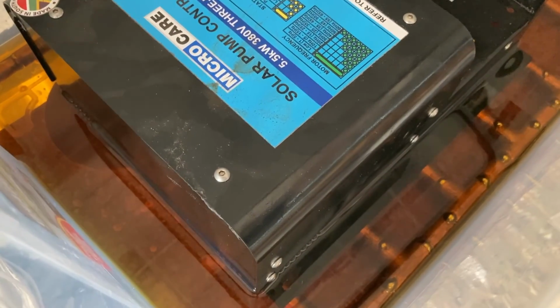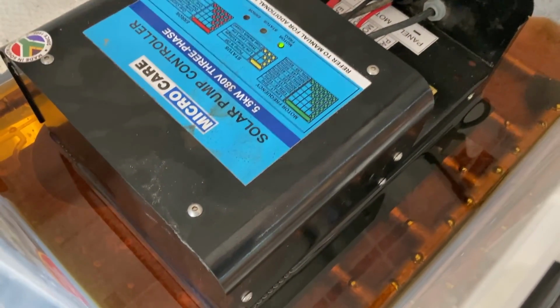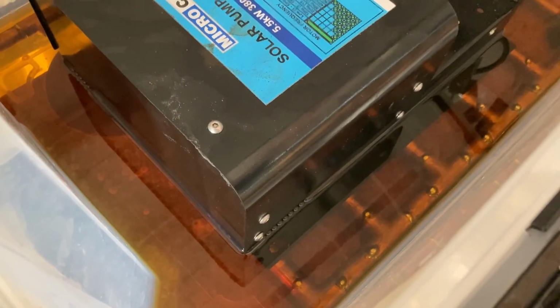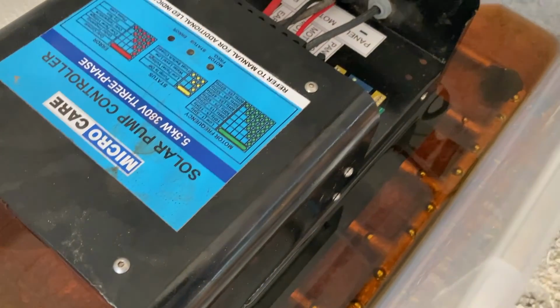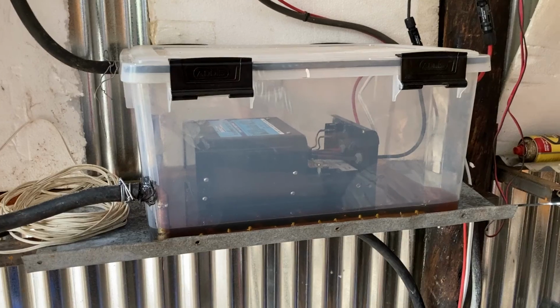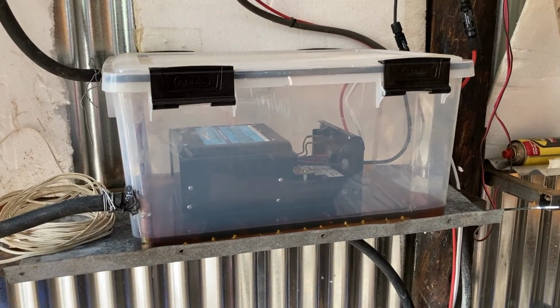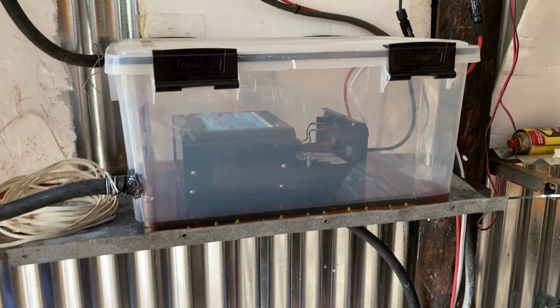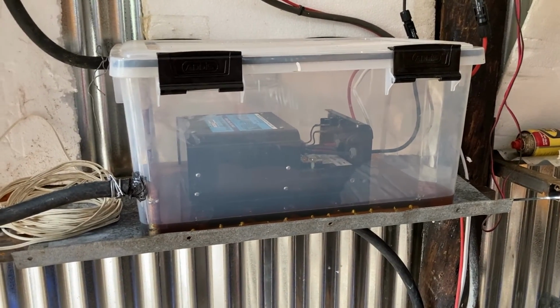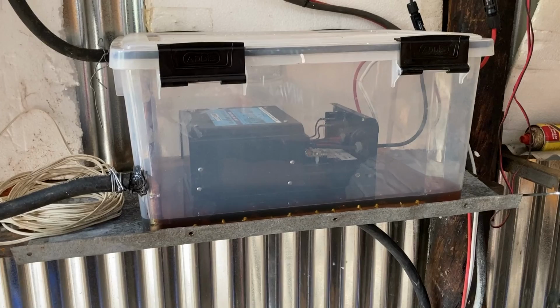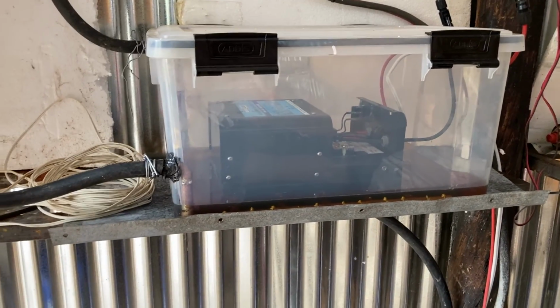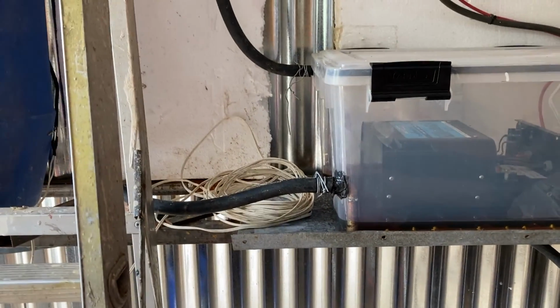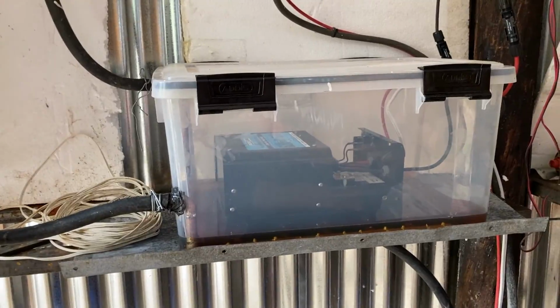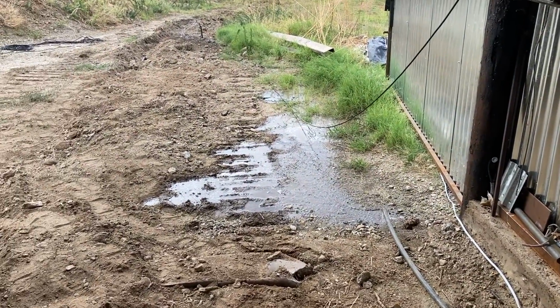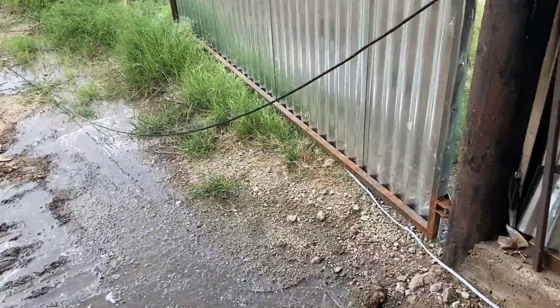And beneath it you'll see the solar pump controller is sitting on a series of copper pipes which I've soldered into a heat exchanger. So the heat transfer occurs through the oil from the fins on the back of the heat sink, because those fins are sitting in oil, and then the oil in turn is cooled by the water which circulates through. And seeing as you're pumping water with this device, there's no shortage of water normally on site. Here you'll see the flow rate that I'm using.